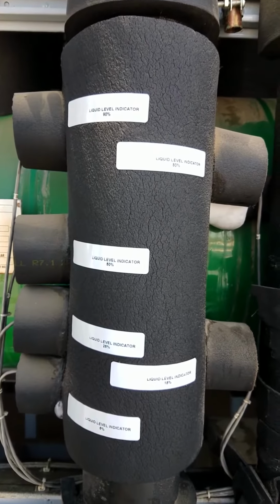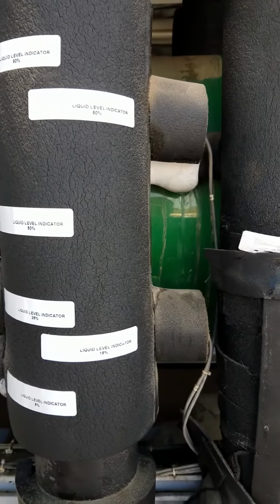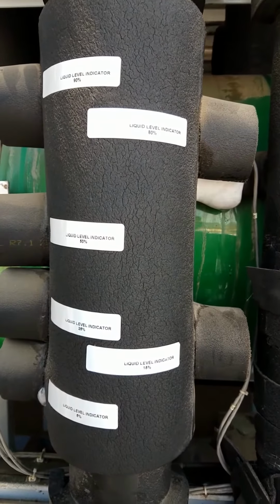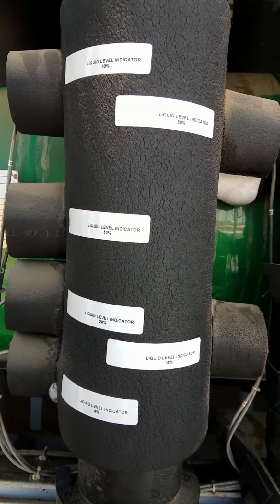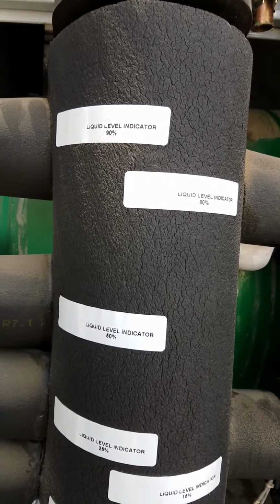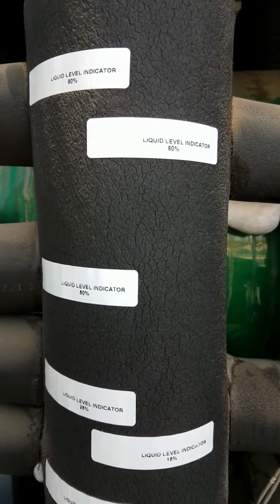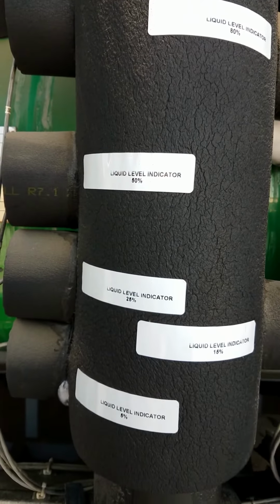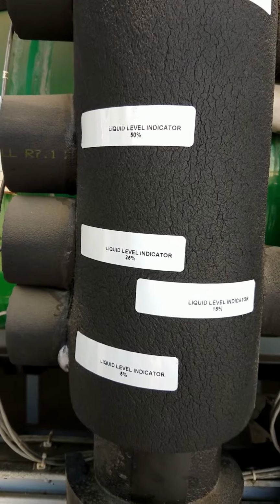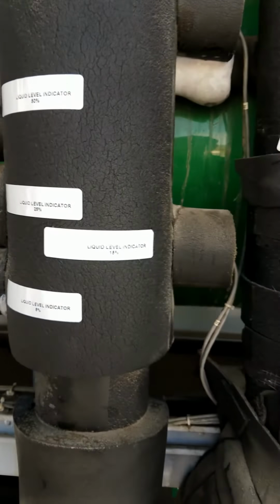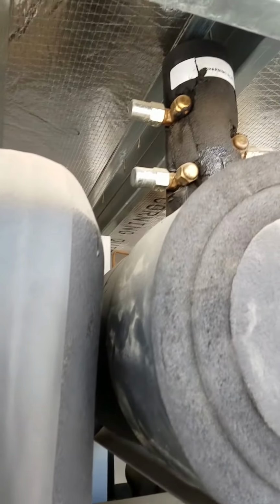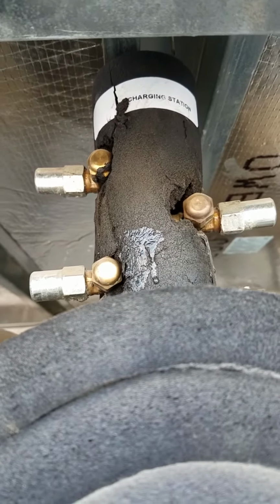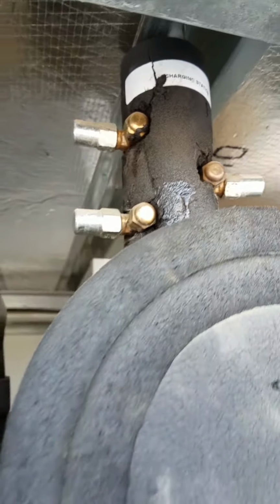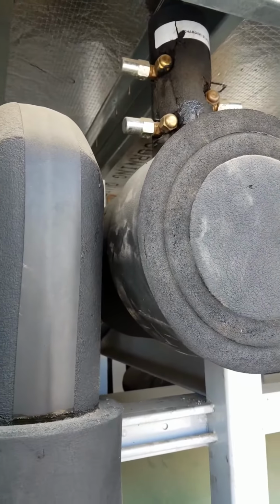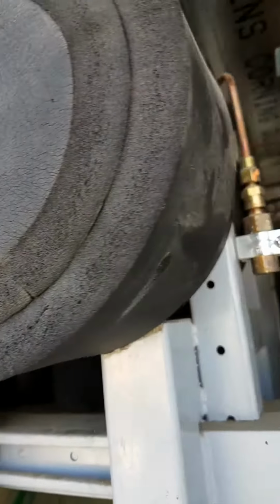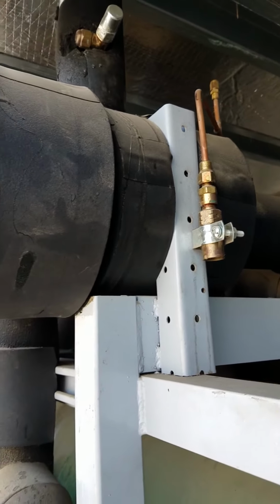And then you got your liquid level indicators. These are sensors. These are high voltage on here, it's not low voltage. You got your 90%, which you never want. Usually they want the liquid level about 25%. That's what we try to maintain it at. And then up here you got your charging tree to charge your CO2 liquid, then the insulated liquid line dryer right here.